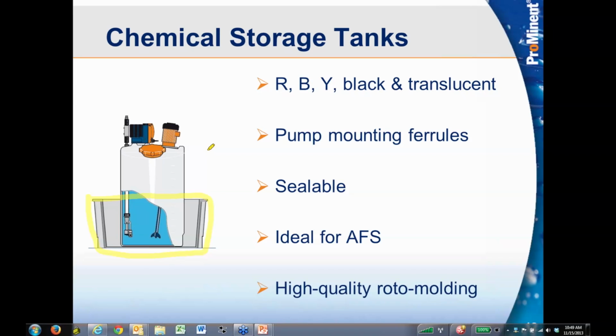Now, understand this though, most of the double wall tanks are not completely sealable. They have air gaps between the lips. So some of them will have the ability to pass acid fumes out, whereas ours can be completely sealed. The other benefit of our tanks is that they come with brass ferrules mounted in them to match up with the footprints of our various dosing pumps, the Concept, the Beta, etc., so that you can mount the pump directly to the top of the tank and offer a nice package solution to the customer of a pumping system along with our controllers.